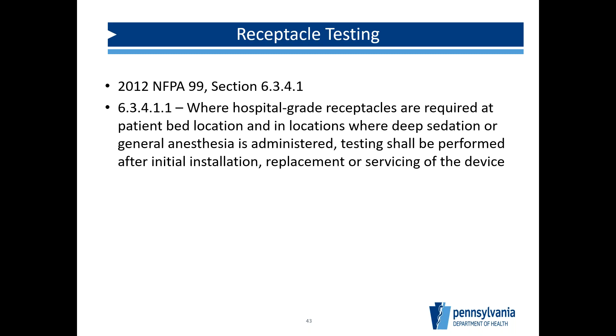So what they're saying here, I gave the section of NFPA 99, is that you have to test the receptacles at intervals, and they talk about defined by documented performance data. But the biggest thing that you want to see here is receptacles not listed as hospital grade in patient bed locations and resident bed locations shall be tested at intervals not exceeding 12 months.